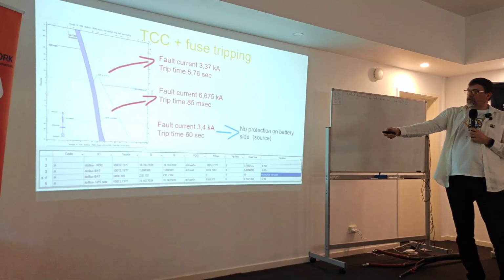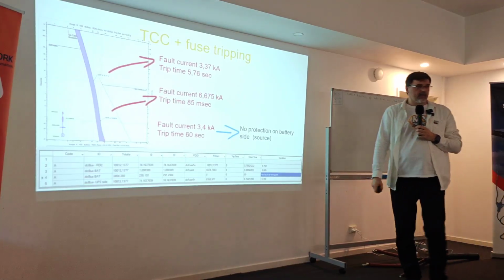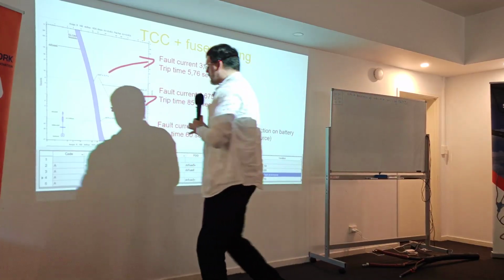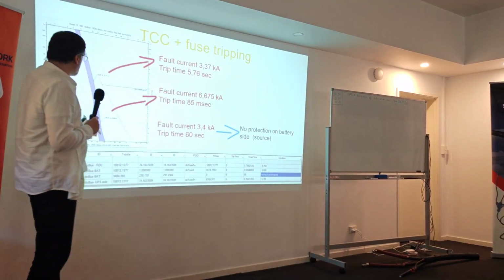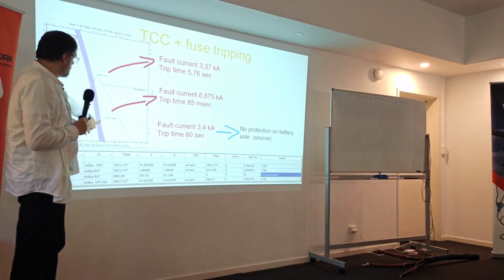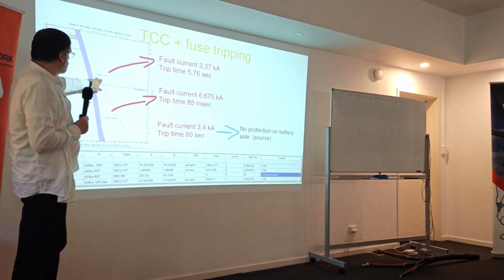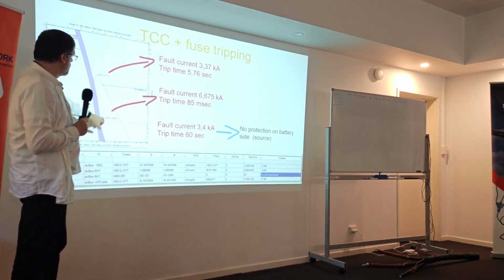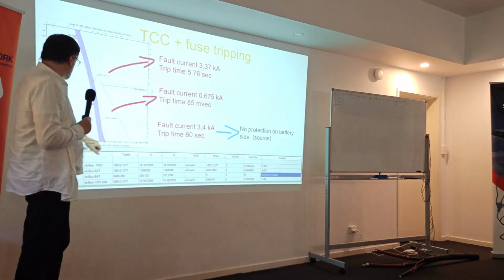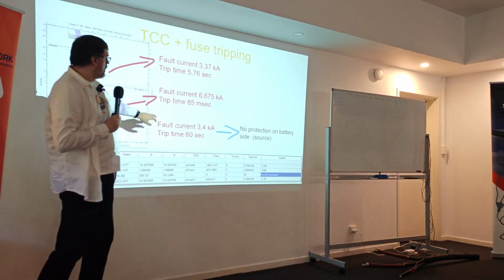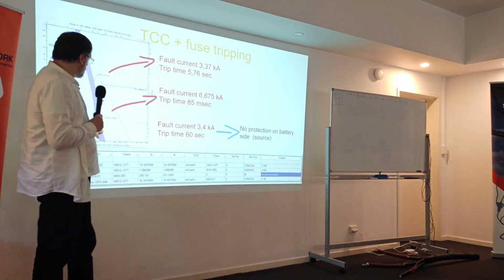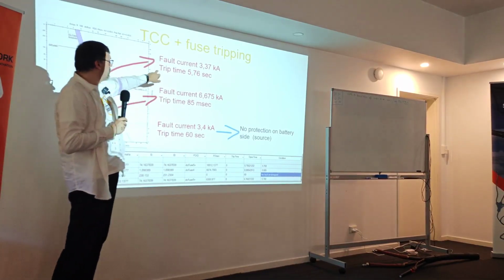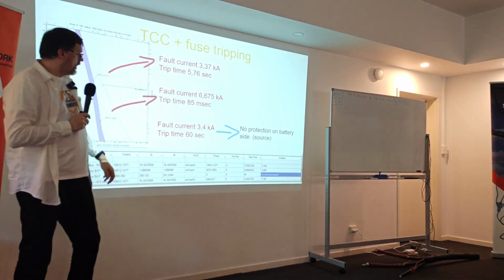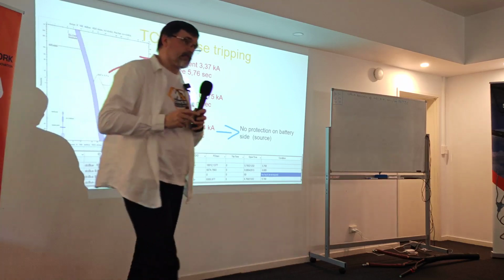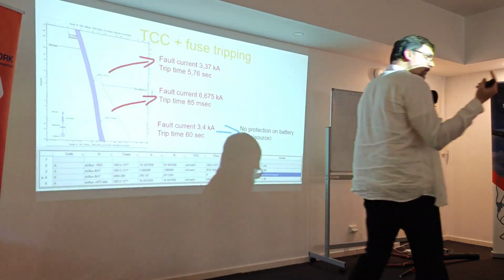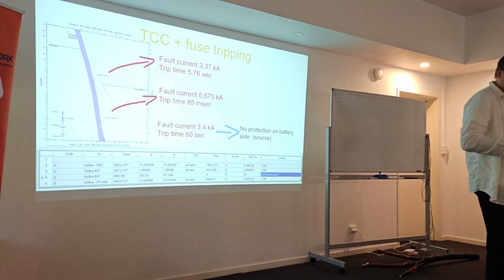So that's how it looks from the protection perspective. It's an AC fuse, not a DC fuse; I have to remodel it for the DC purpose. If you check the short circuit current, you have two steps, depending on the tripping time: 3.3 and 6, and there was one more that we'll calculate later. You can see the trip time for the 6.6 for the short circuit was approximately 85, but for the arc one it was 5.7. And there is no protection on the battery side. Sometimes batteries have protection built in between the racks, but not in this one.